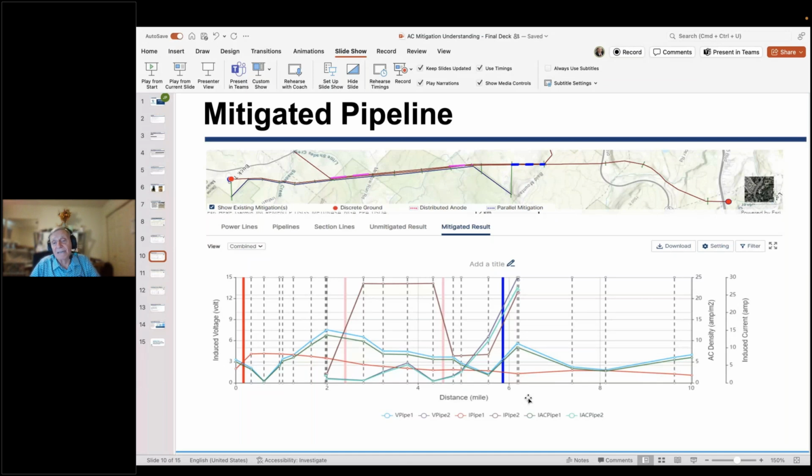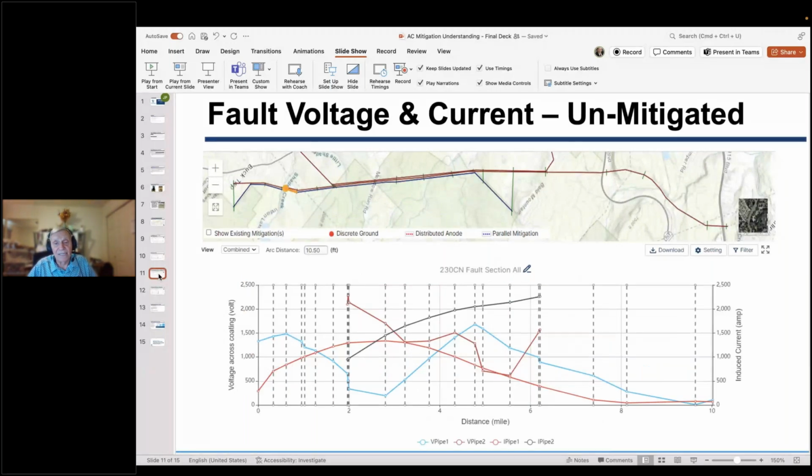Their payback on that is going to be within 6 months. So could you imagine taking a 1500 amp system and running it up to 4500 amps or 5000 amps, whatever, with the same conductors? And what do you think that's going to do to your pipeline? That's what I'm going to talk about next year in Nashville. Reconductoring remote and co-located locations. So watch out for that. I'm putting that paper together as I speak. So I just wanted to point that out, but just to show you how quickly you could mitigate things.